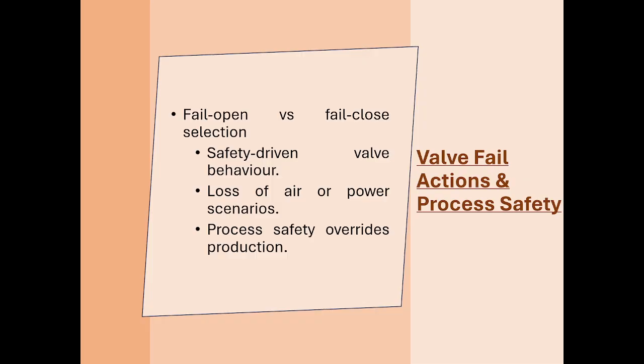Let me slow down here with a simple picture. Imagine you are on site and suddenly there is a power failure or the instrument air supply drops. At that moment, the control system cannot think or calculate or ask questions, so the plant must already know what to do. That is what valve fail action means. A valve can be designed to fail open, fail closed, or fail in its last position when power or air is lost. This decision is not about production or convenience, it is purely about safety, protecting people, equipment, and the environment. This is why process safety always overrides production targets.